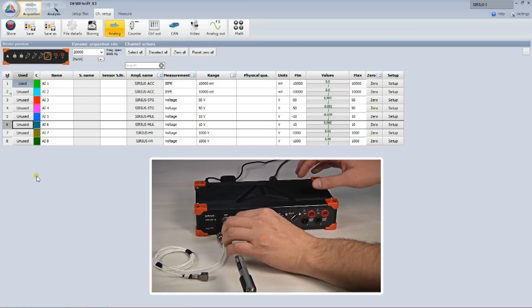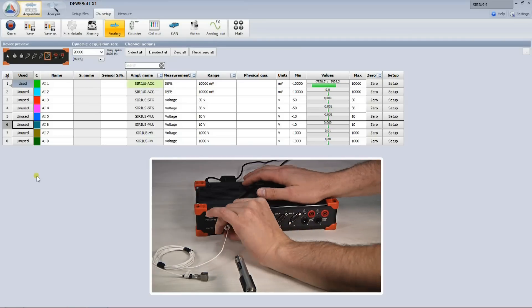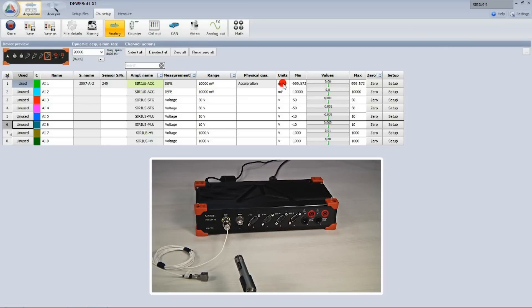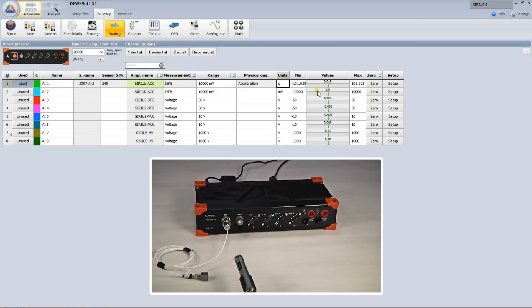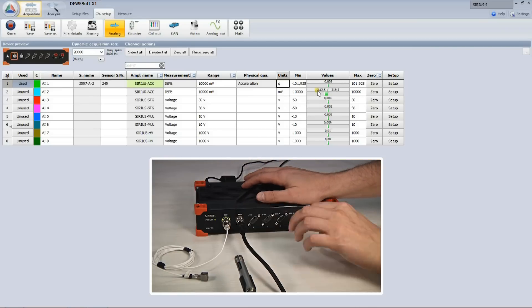On the first channel, I connect an accelerometer which has a smart sensor interface called TEDS, and the sensor's type, serial number and sensitivity is immediately recognized. I am free to choose the unit of measurement, because Dewesoft X has automatic physical unit conversion. Then I connect the microphone, which is also recognized.